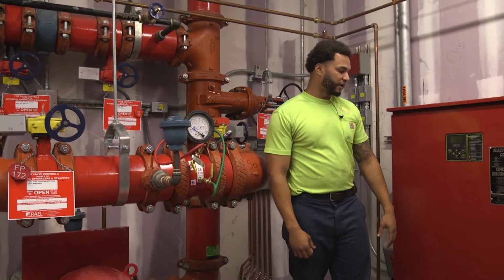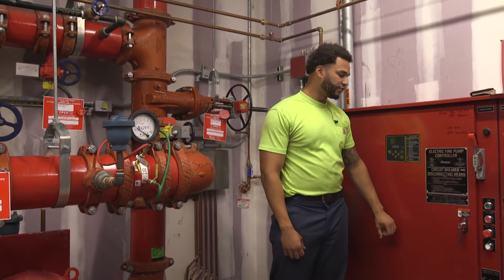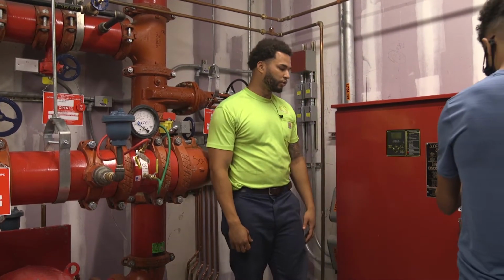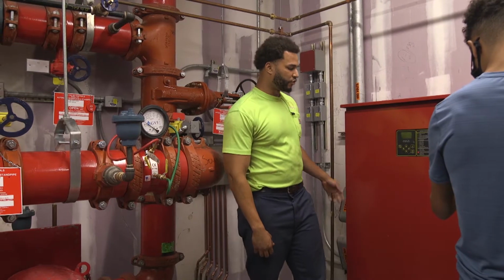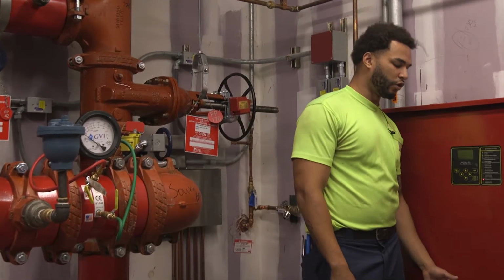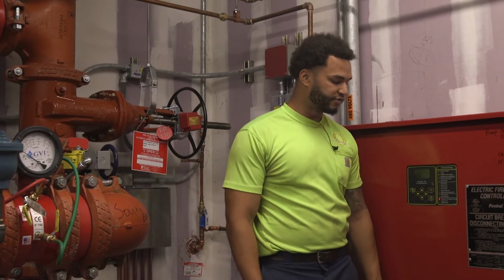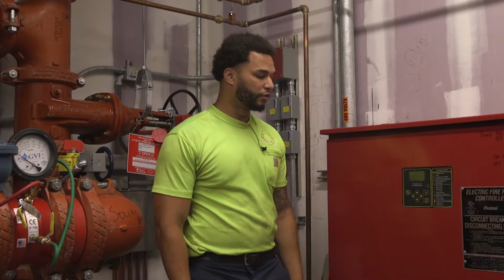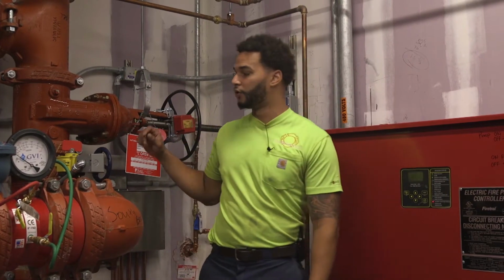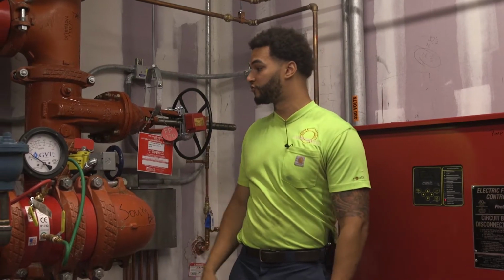Our fire pump controller is actually a FTA 1930 fire control soft start controller. When I say soft start, that means this fire pump is going to slowly start up and slowly stop. The reason for that is to reduce the mechanical stress put onto the fire pump system when your fire pump first starts up.